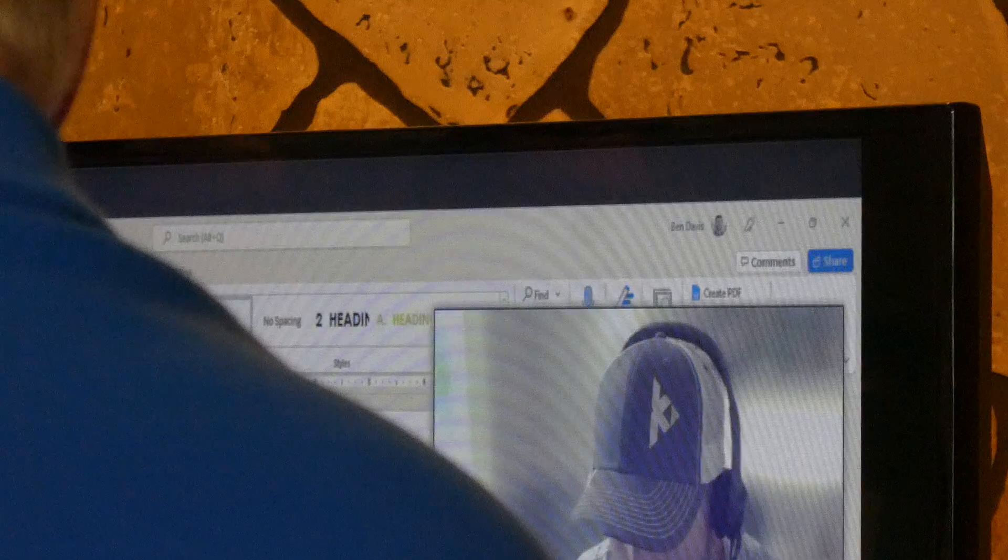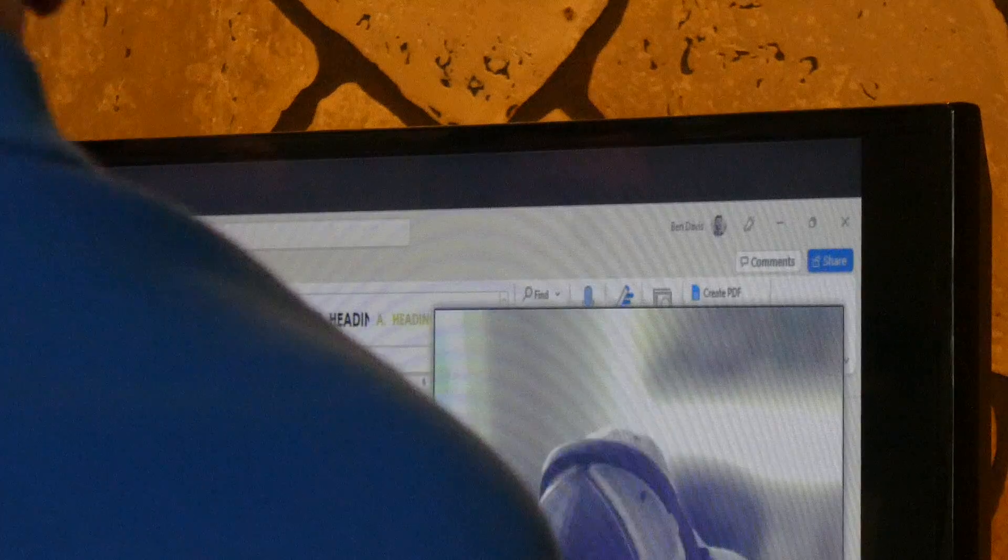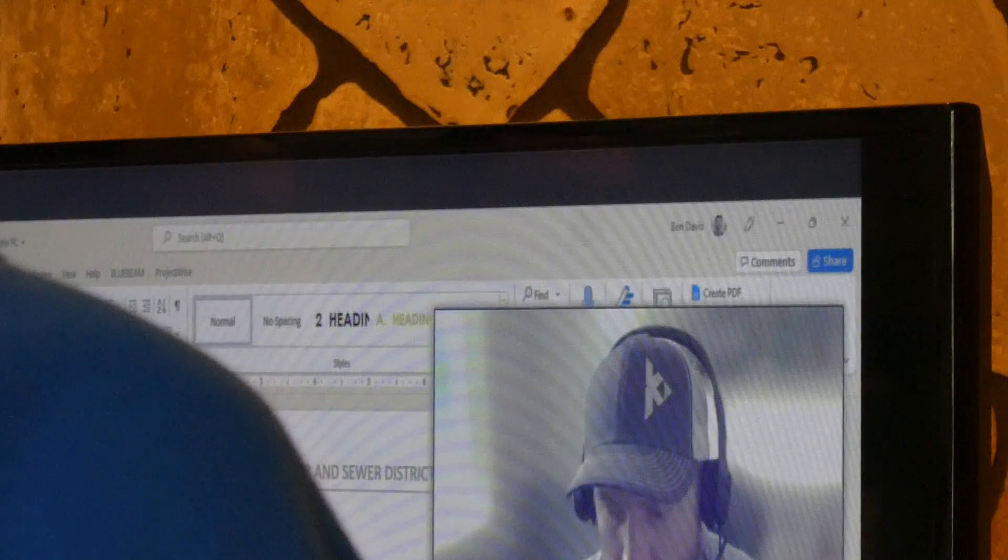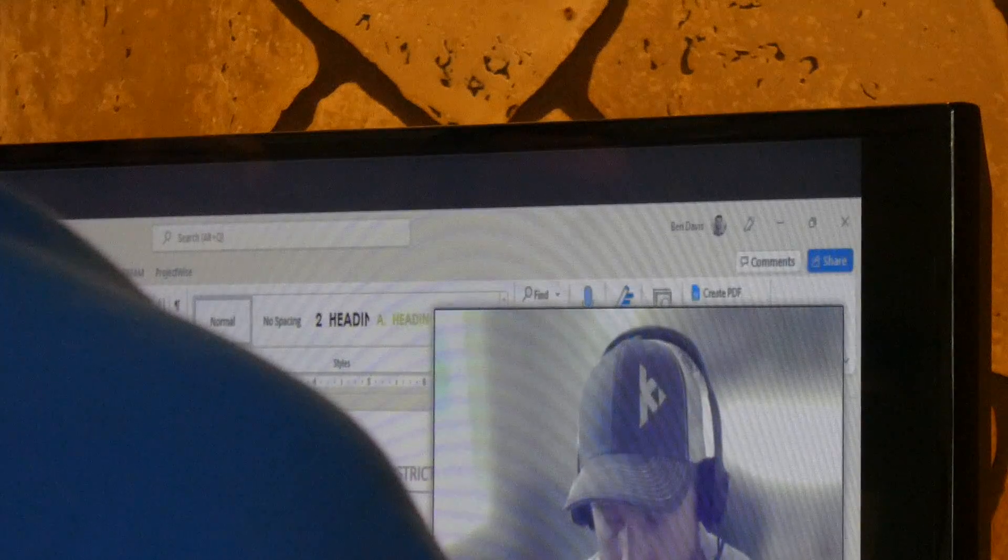Ben, can I give you some input on that, and that is, right now, we've been kind of, I want to say, nickel and diming with a banner system we've had in there for 20 years. It seems like they don't handle the foliage growth or people growth in here in the area, the 900 MHz spectrum tends to get interrupted. But, the point is, right now, since our last repair, we've actually been holding up pretty good with it. But, if something goes on that to where we're in trouble, and they don't have parts, then, suddenly, we're forced into a situation with this new SCADA system.